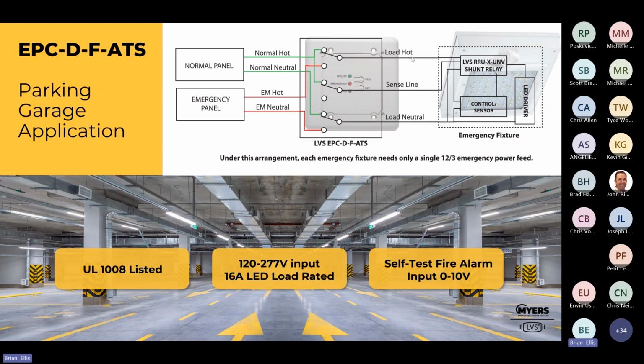So then your load hot and your load neutral will always either be utility or they'll transfer over to emergency, feeding power to this via emergency. But then the sense line will be utility only. So when utility fails and this transfers over, we drop the sense line, allowing this shunt relay to understand it's lost utility. So what we've done is we're still selling all the products that we wanted to sell, but we're helping the contractor by allowing him to eliminate a mile of conduit and only provide 1 conduit instead of 2.